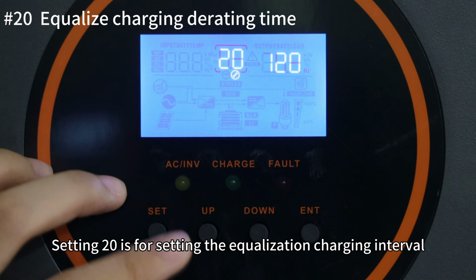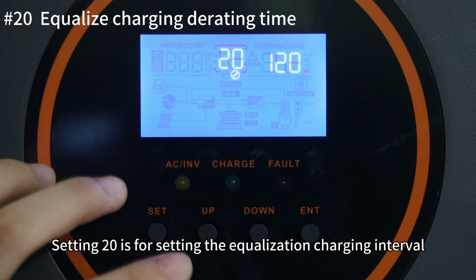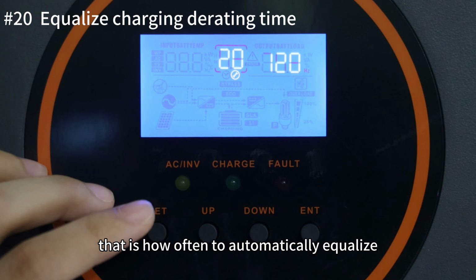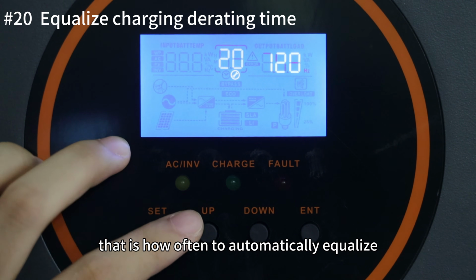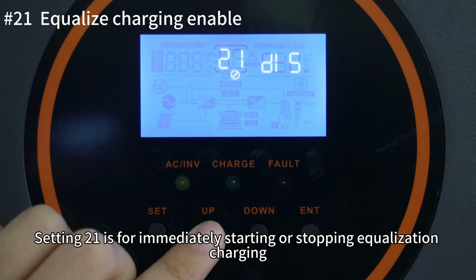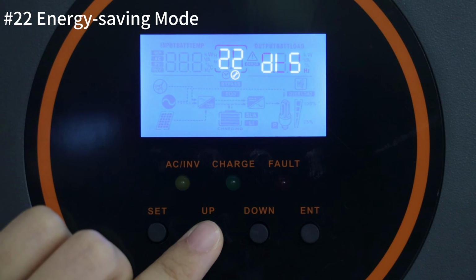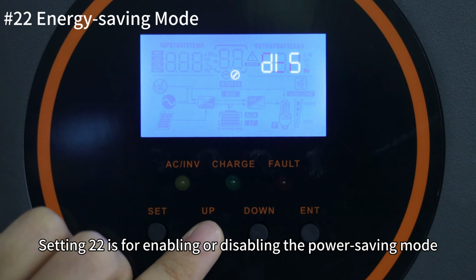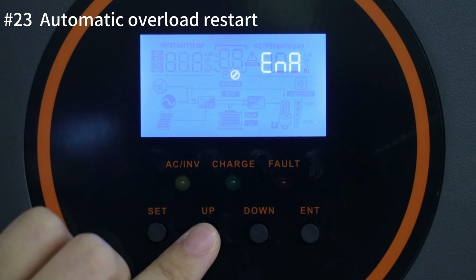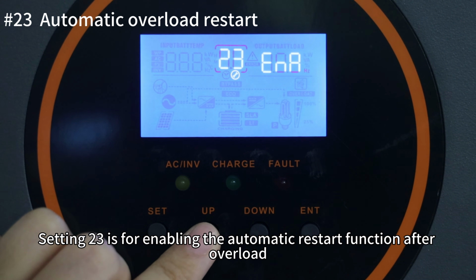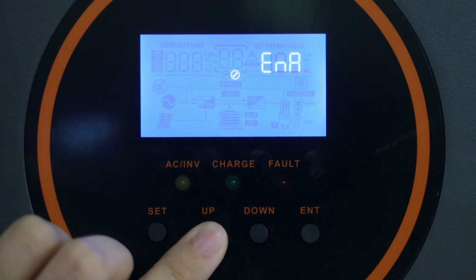Setting 20 is for setting the equalization charging interval, that is, how often to automatically equalize. Setting 21 is for immediately starting or stopping the equalization charging. Setting 22 is for enabling or disabling the power saving mode. Setting 23 is for enabling the automatic restart function after overload.